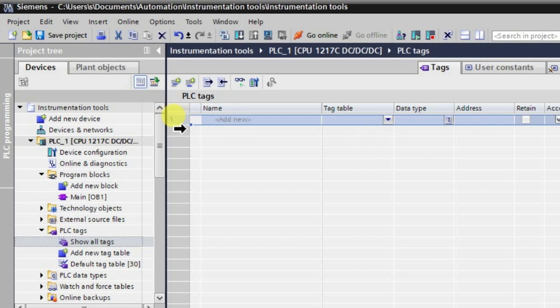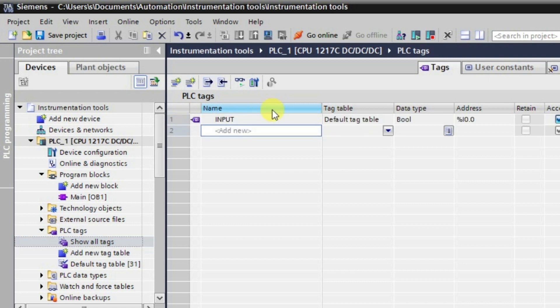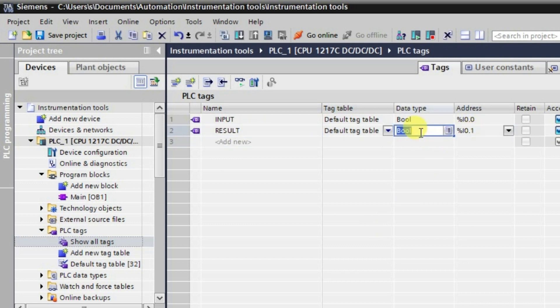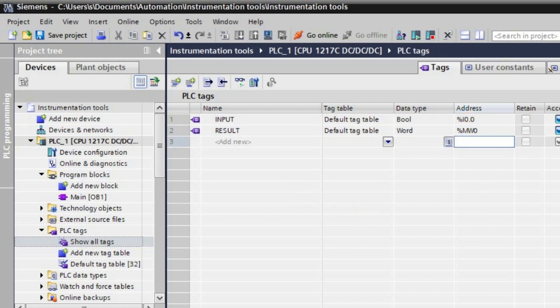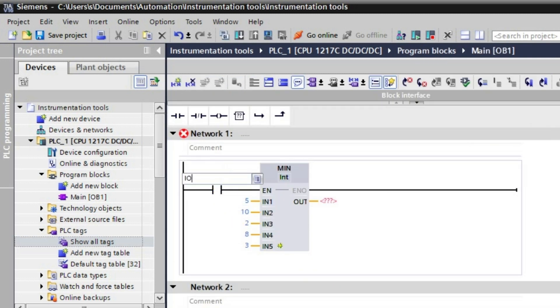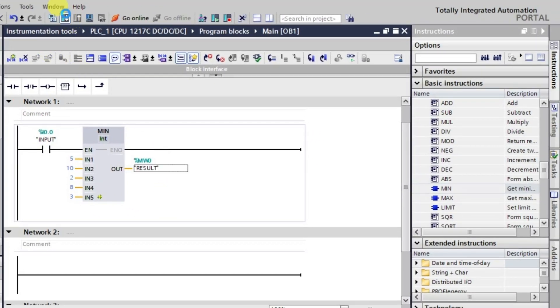The result will be stored in a memory word. I'll create a tag called 'result' with data type WORD and address MW0. The input will be I0.0. These are all the various inputs to the function and the result will be stored in MW0.